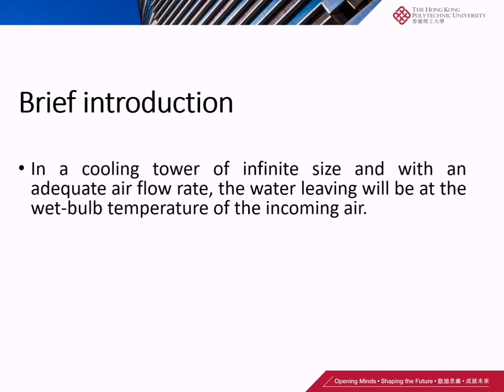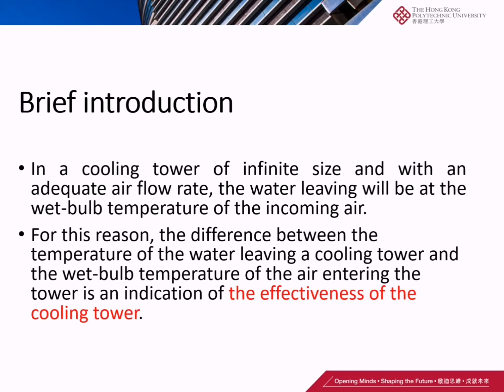In a cooling tower of infinite size and with an adequate air flow rate, the water leaving will be at the wet bulb temperature of the incoming air. For this reason, the difference between the temperature of the water leaving a cooling tower and the wet bulb temperature of the air entering the tower is an indication of the effectiveness of the cooling tower.